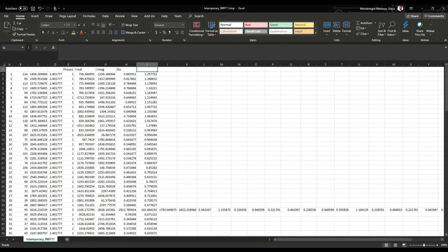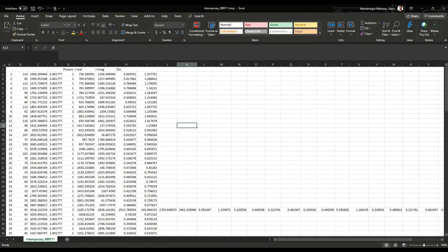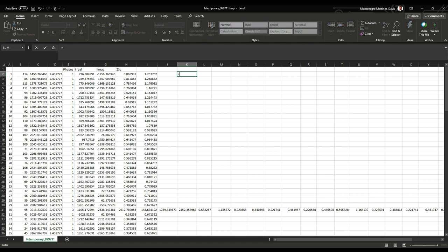And we can verify it here. So for example, for the first bus that we have, this is a single phase bus, we're going to calculate the magnitude of the short circuit current using the elements that we have by hand.